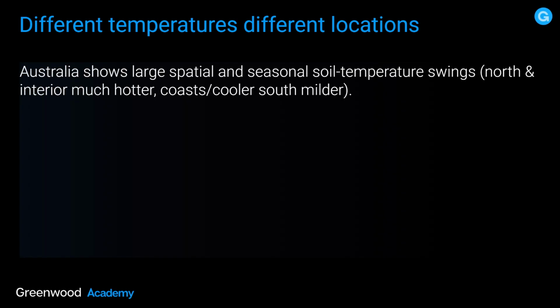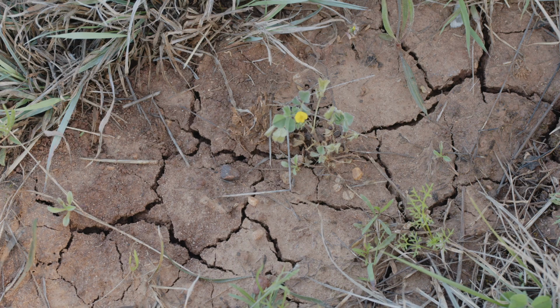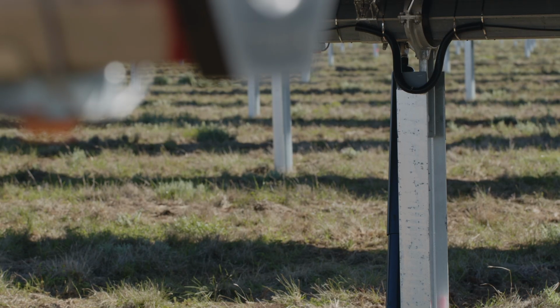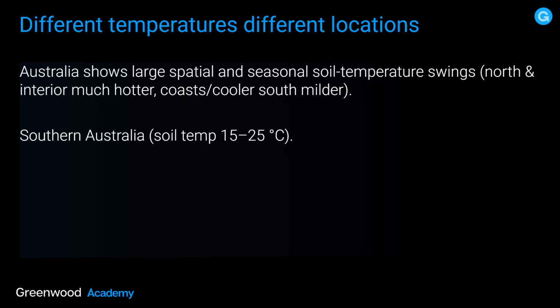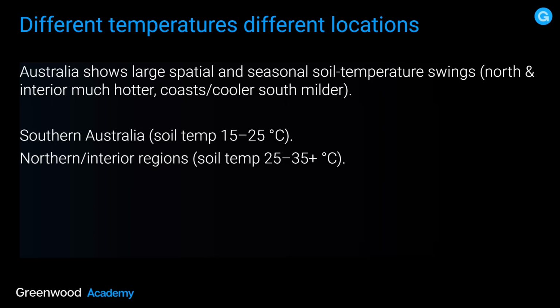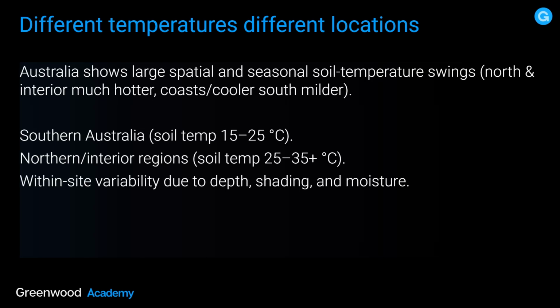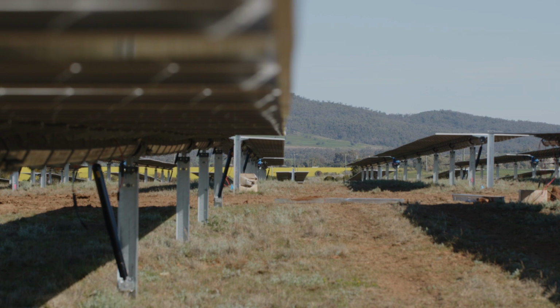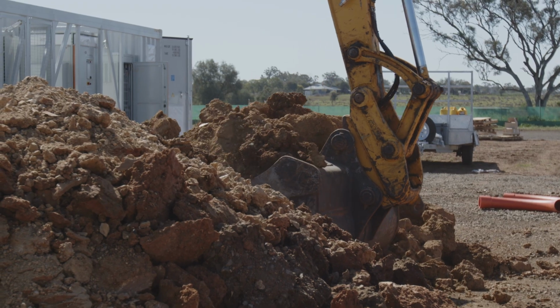Australia shows large spatial and seasonal soil temperature swings, north and interior much hotter, coasts cooler, and the south being much milder. In southern Australia, the soil temperature can range between 15 and 25 degrees C, but in the northern interior regions, the soil temperature can be 25 to 35 degrees plus centigrade. And also, there's going to be within-site variability due to depth, shading, and moisture. So it's not only the soil temperature that plays a role in the current carrying capacity of the cable. It's also the kind of soil we're talking about and its moisture content and how deep the cables are actually buried.